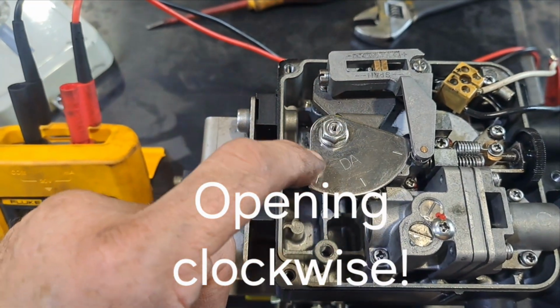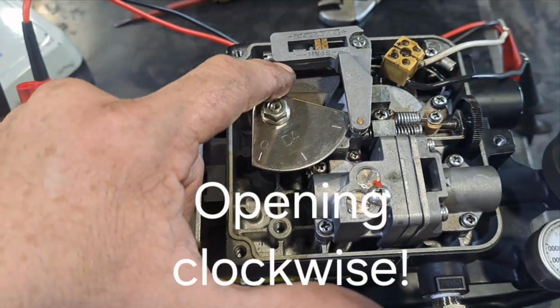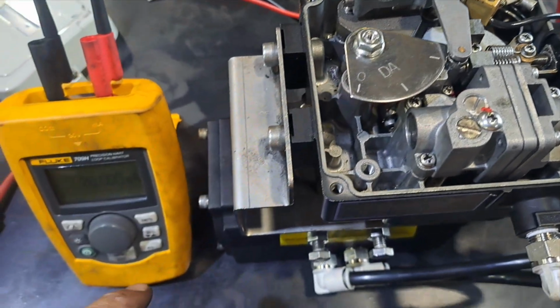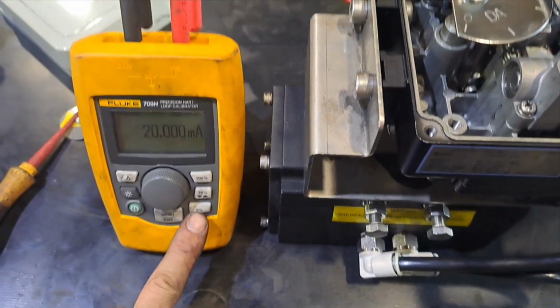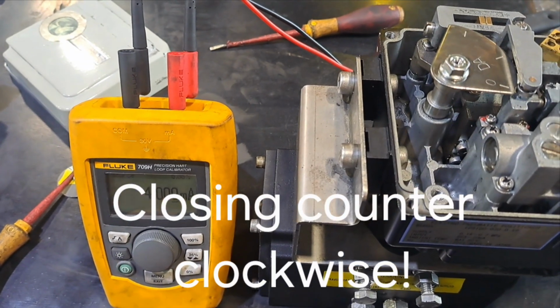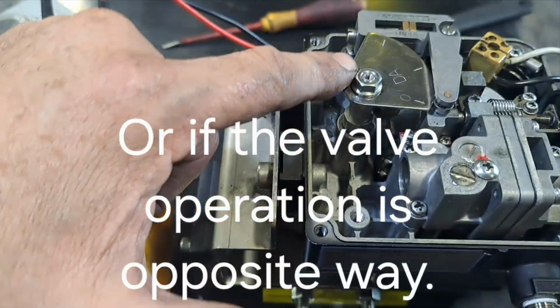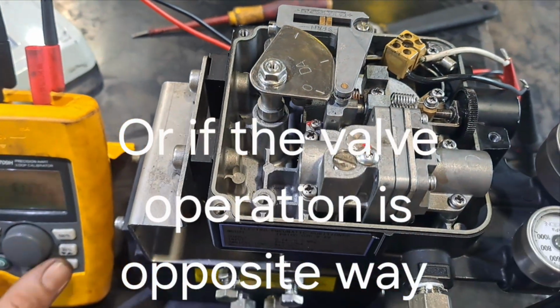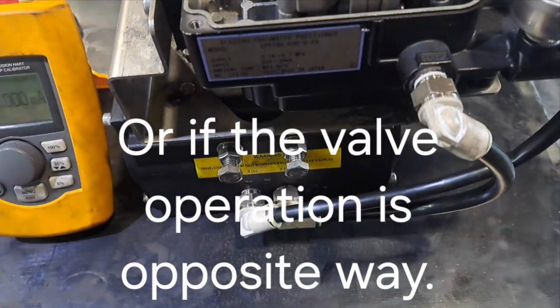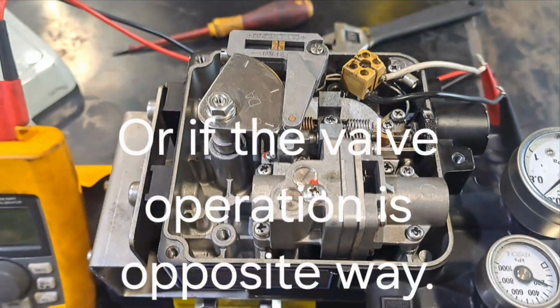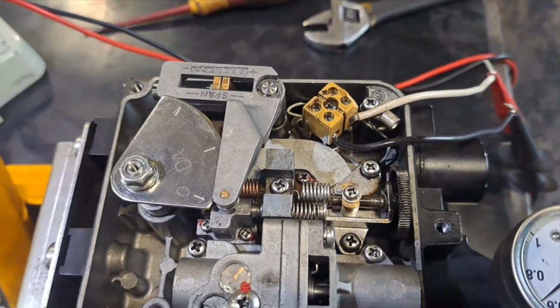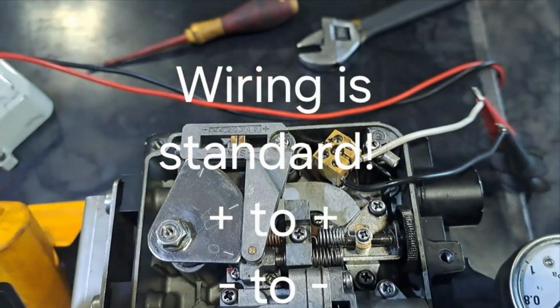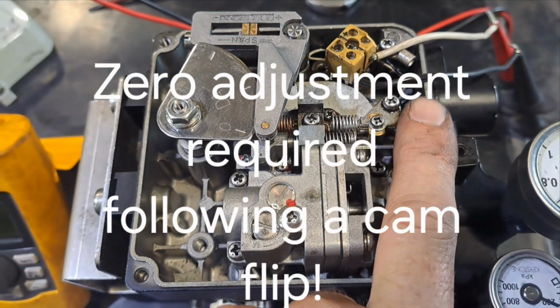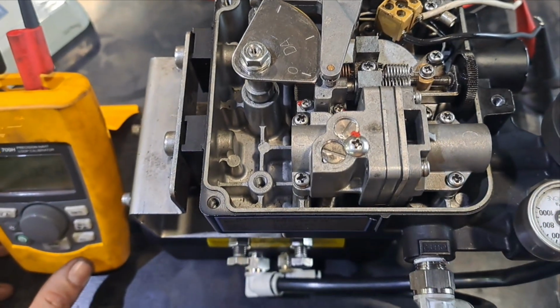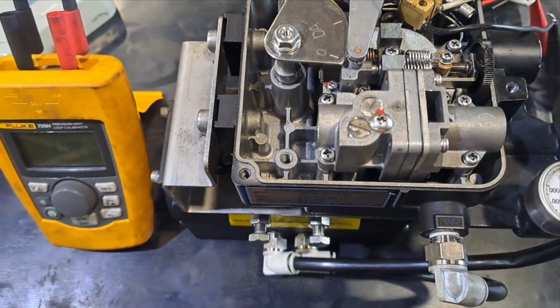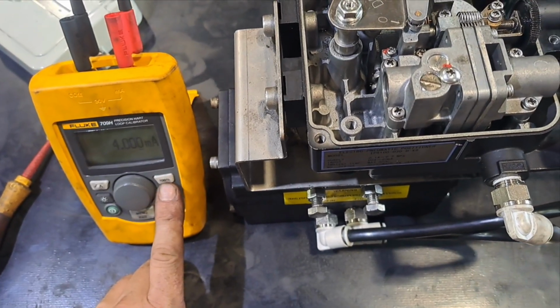With this second setup, what we're really doing here is opening and closing in opposite directions to what is standard. The only reason why you would do this is if you have a cylinder and you can't put the positioner where you would like to put it to keep everything standard, you might have to put it on the other side, which means your in and out, left and right, open close movement turns out to be non-standard for your positioner movement. Our failsafe is still closed. At this point, it's just that we're going in opposite directions from our standard.